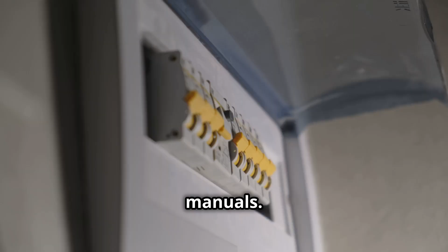Once the energy sources have been identified, the next step is to isolate them from the equipment. This may involve shutting off circuit breakers, disconnecting switches, closing valves, venting pressure, or physically blocking moving parts. The key is to ensure that energy cannot flow to the equipment while work is being done.